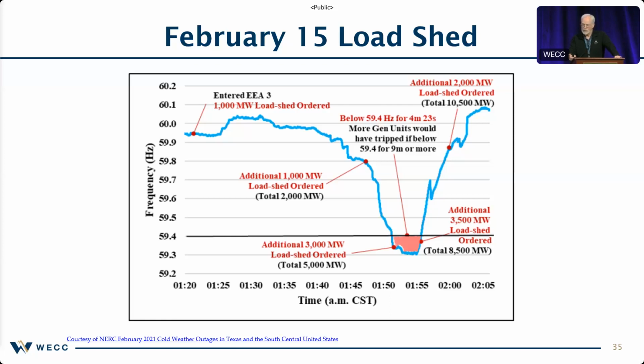As the frequency is recovering, more generation is lost. You can see the dips that go down on that frequency, and they order another 2,000 megawatts of load shed. So in this particular 45-minute period, they went from 0 megawatts to 10,500 megawatts of load shed. Over the course of this event, ERCOT would eventually shed 20,000 megawatts of load, the largest load loss from load shed in the country and rivaled only by blackout conditions that have occurred in different areas of the country.